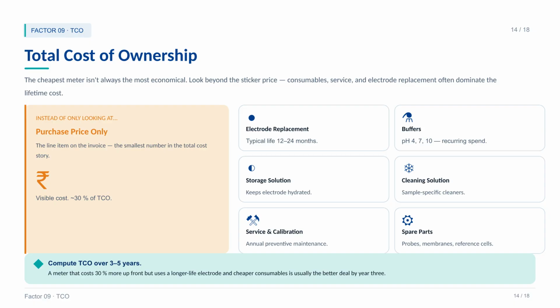Factor 9. Total cost of ownership. The sticker price is just the beginning. You also need to factor in electrode replacement every 12 to 24 months, buffers, storage solution, cleaning solution, annual service, and spare parts. The cheapest meter isn't always the most economical. A meter that costs 30% more upfront but uses a longer life electrode and cheaper consumables is usually the better deal by year 3. Always compute TCO over 3 to 5 years.